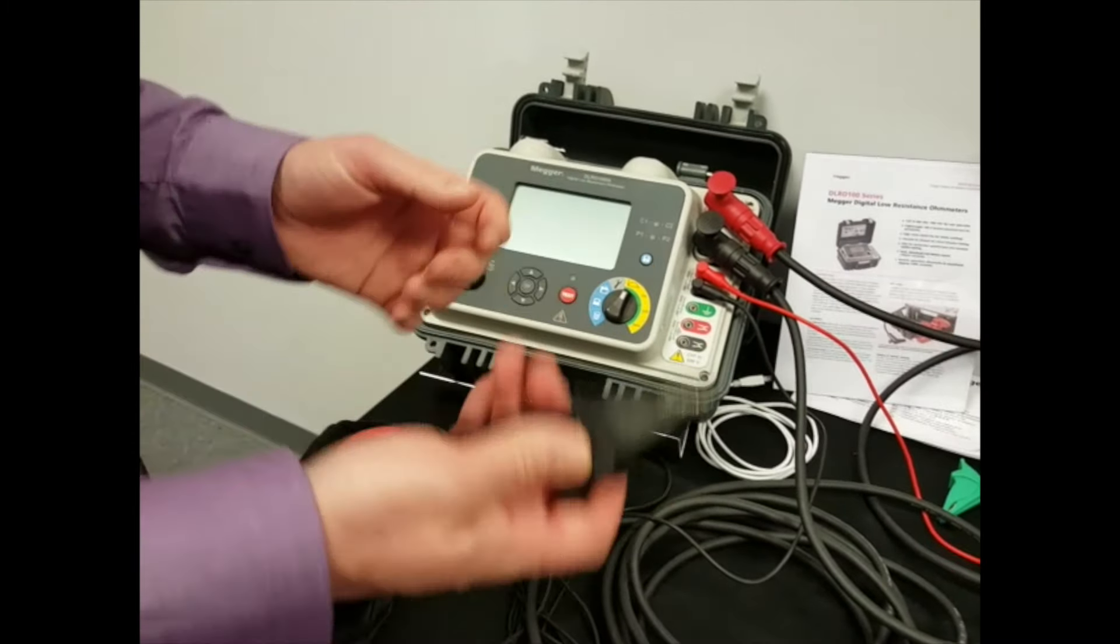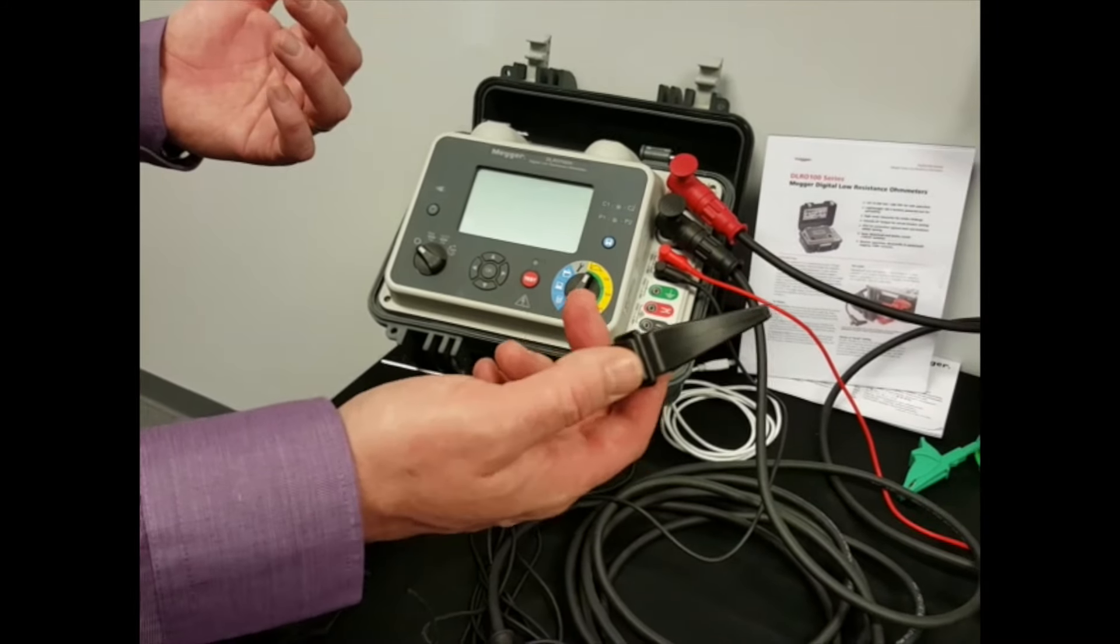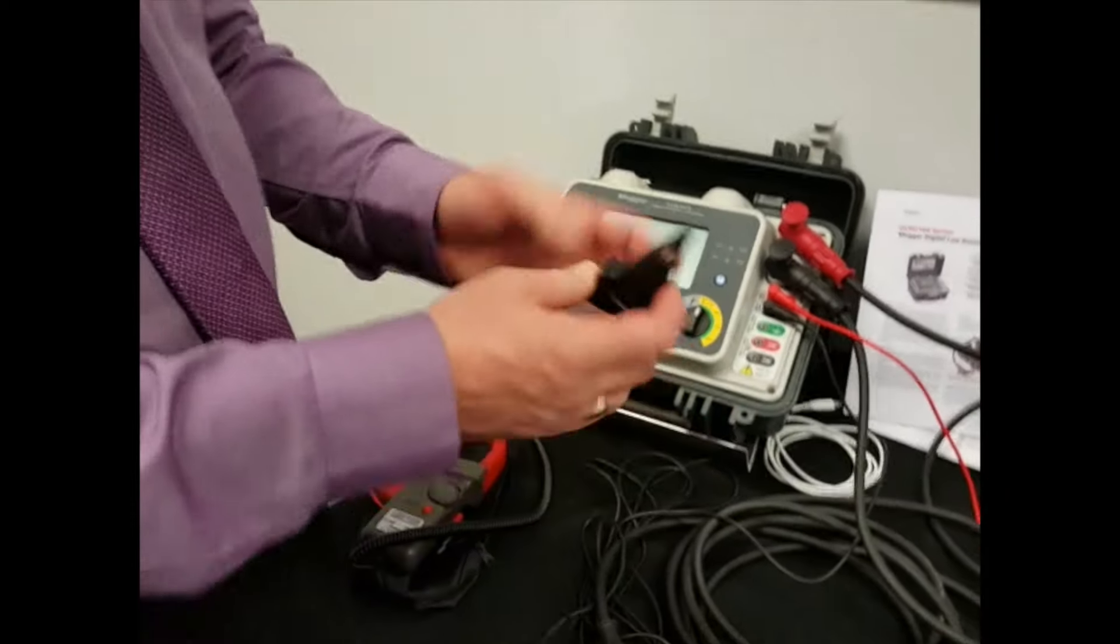Because if I was connected to a bus bar system, the bus bar I'm testing might well be dead, but if there was a live bus bar nearby and a bare clip was to fall off, it could contact a live circuit causing an arc flashover, which is obviously clearly unsafe.